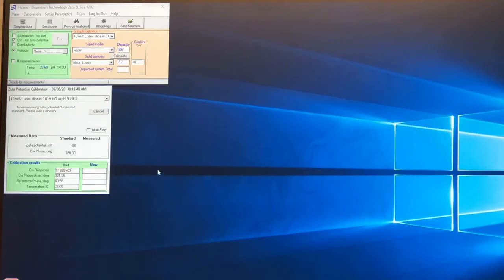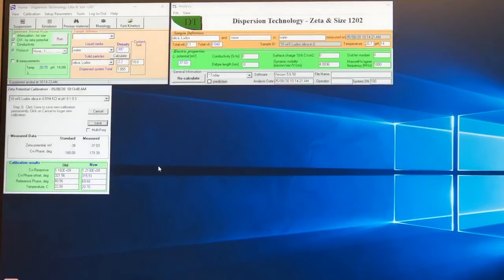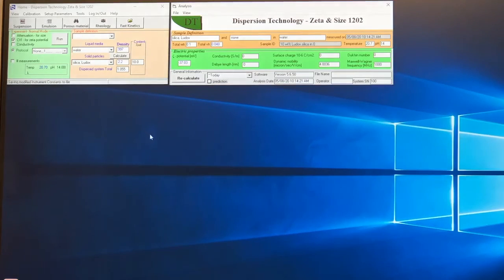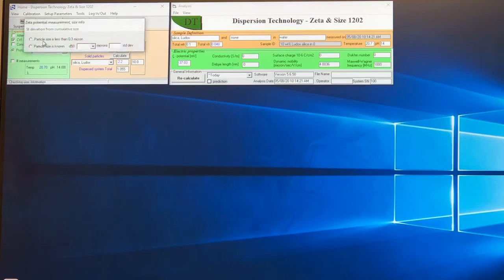The instrument will then perform a calibration measurement. Upon completion, the instrument will report the measured zeta potential and CVI phase. These values should be within 1 millivolt and 1 degree of the standard values. If they are, click OK and you are good to go. If not, press OK and then repeat the calibration experiment until those values are within the acceptable range. Once you've completed calibration, your instrument is ready to go and you can begin making measurements of your samples.